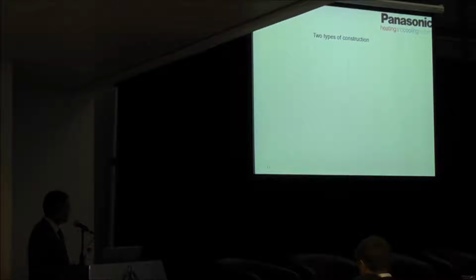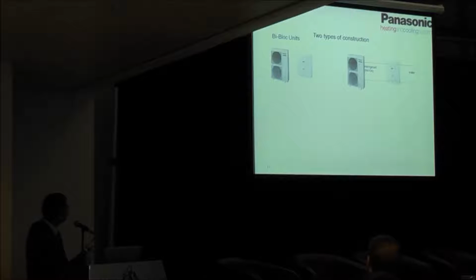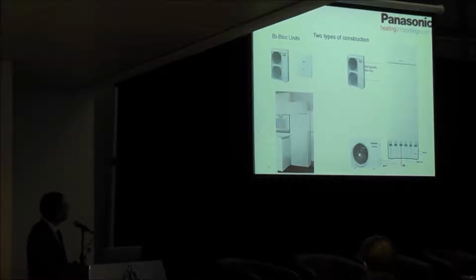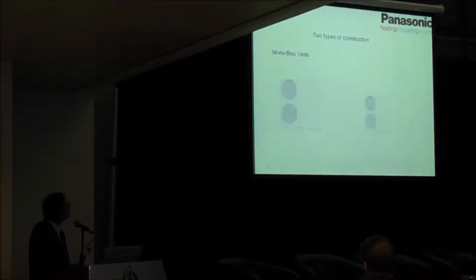In air-to-water units, there's two types of construction. There's what we call a bi-block, where we have, can we see that? An outdoor unit and an indoor unit. And between both, we have direct expansion or refrigeration pipework. And then we have our plumber's copper going around the system. There's new units also which have a combined cylinder and hot water tank. Then there's monoblock units which comprise the indoor and the outdoor unit all together. It all sits at the outdoor unit, so the pipework going into the building is through plumber's copper only.